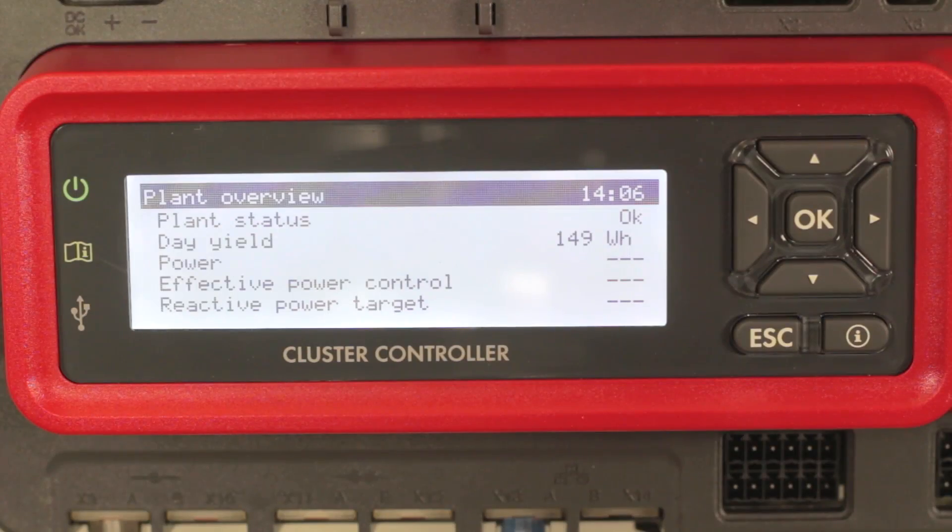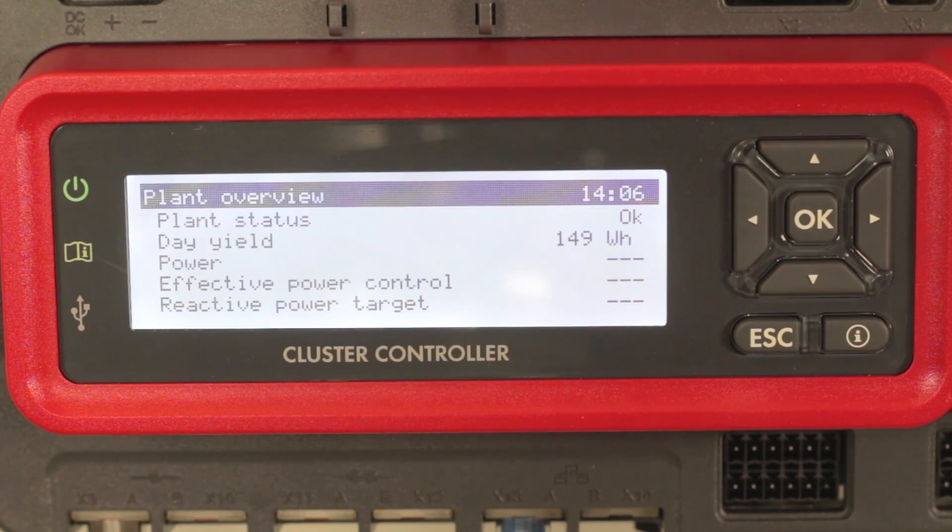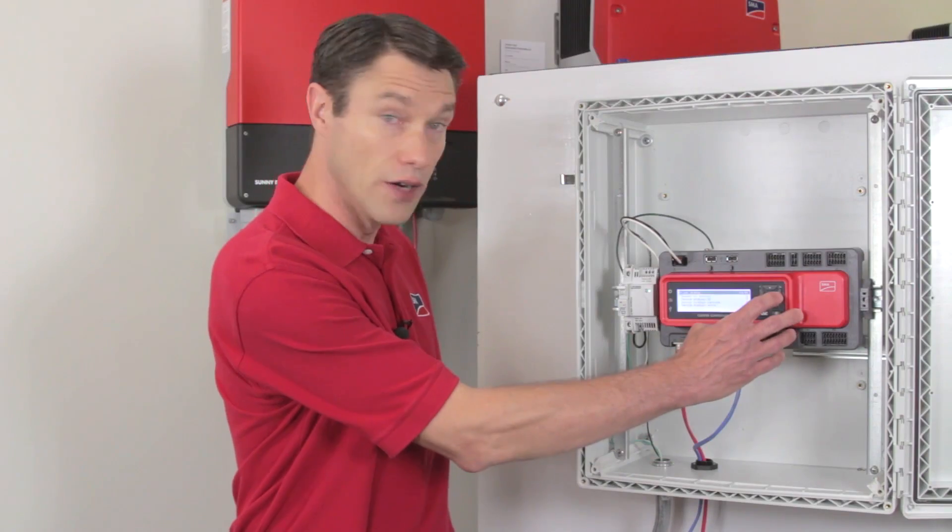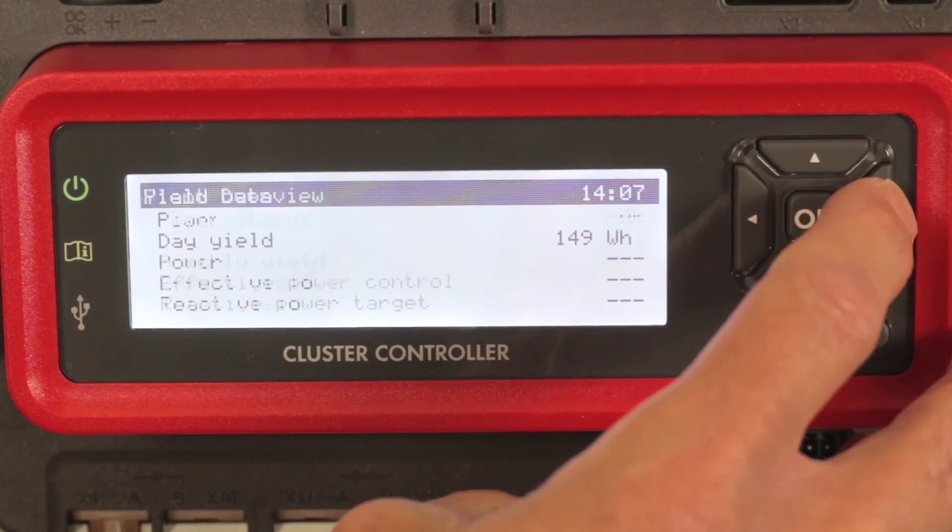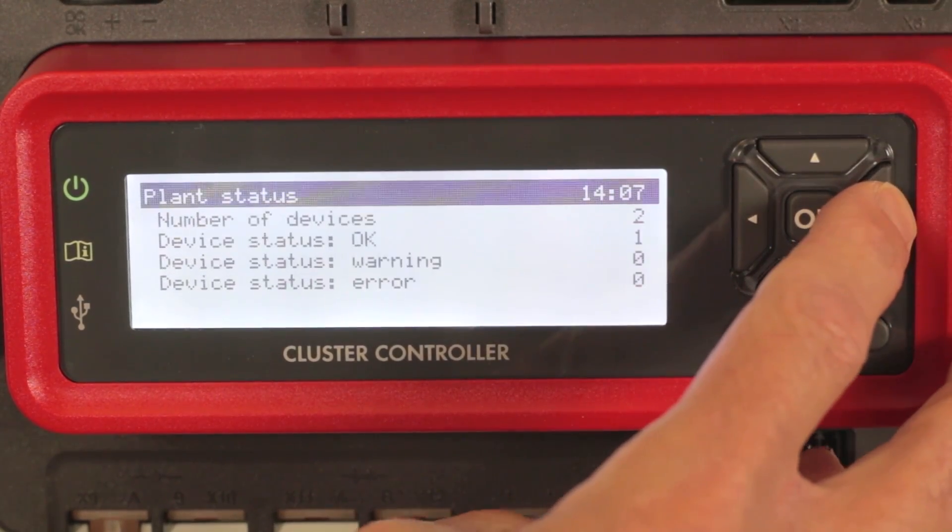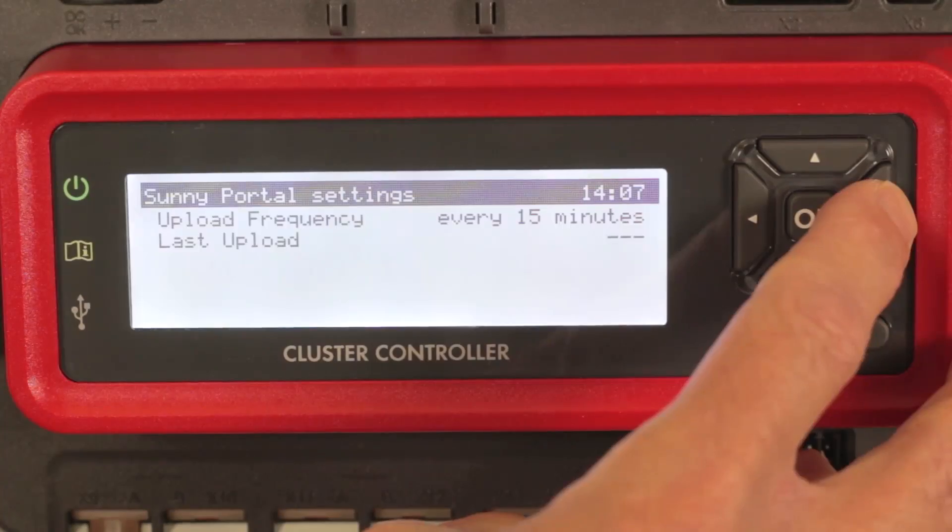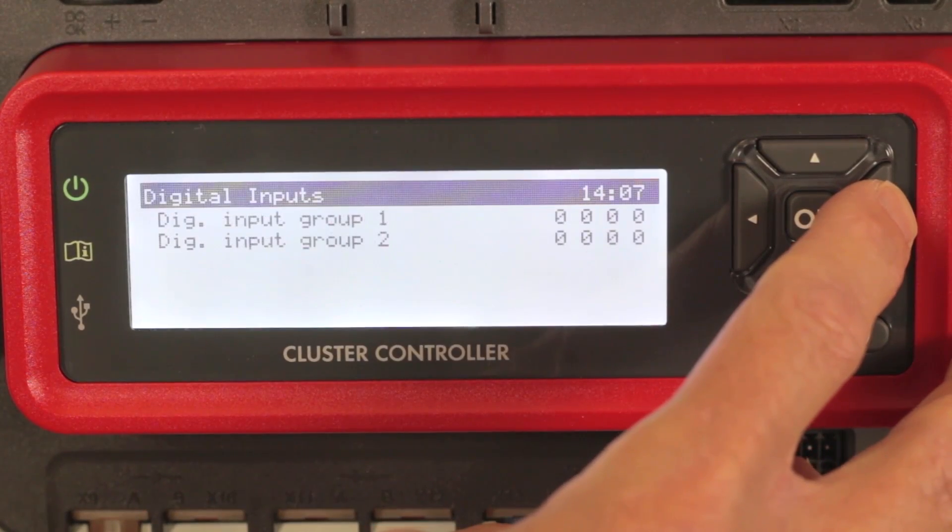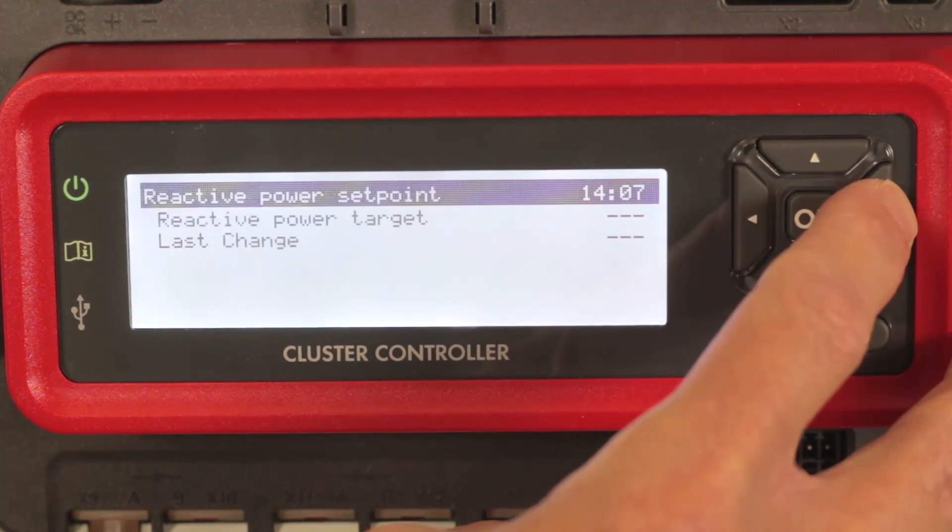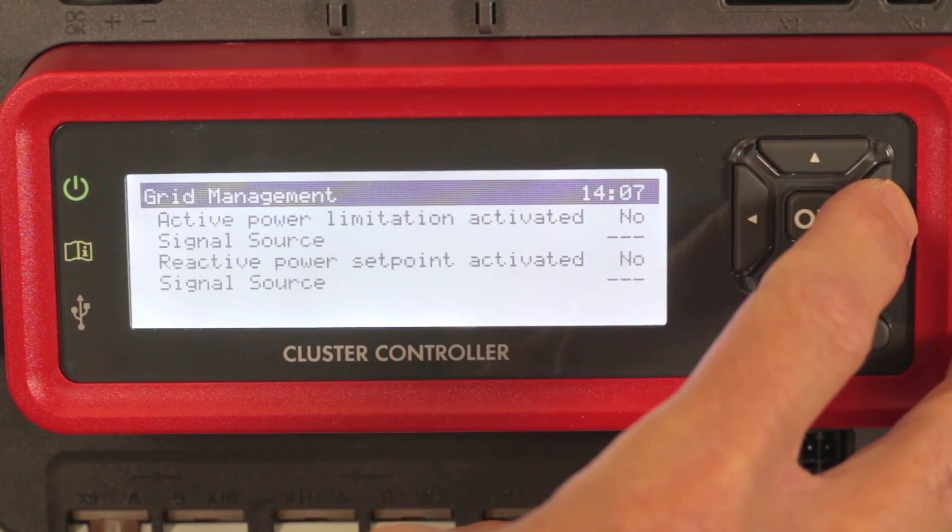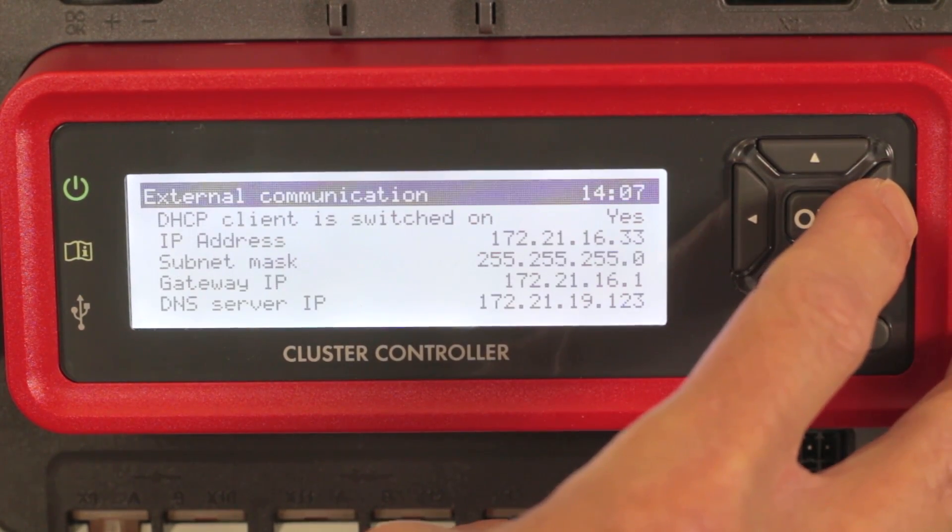Once the cluster controller has fully booted up, the power LED should be green. And now you can cycle through the display screens, of which there are 14. The one that's of most importance is titled external communications, and it will show the IP address that has been assigned to the cluster controller. You'll need this for accessing the user interface.